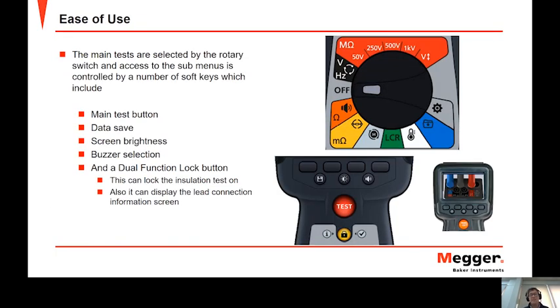So ease of use is key with the MTR105. All of the tests are selected by the rotary switch. And then within each test, access to the submenus is controlled by soft keys. And these include the main test button that we see down here. We have a save button. We have a screen brightness button. We have a buzzer selection, so we can set a buzzer to sound at certain times.